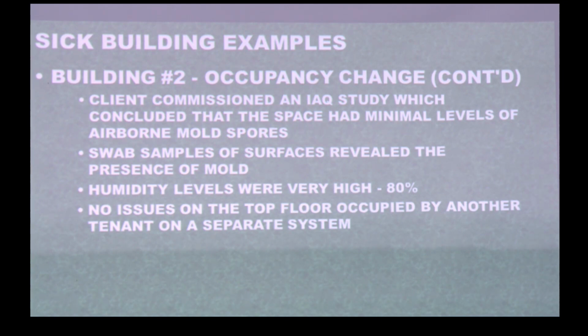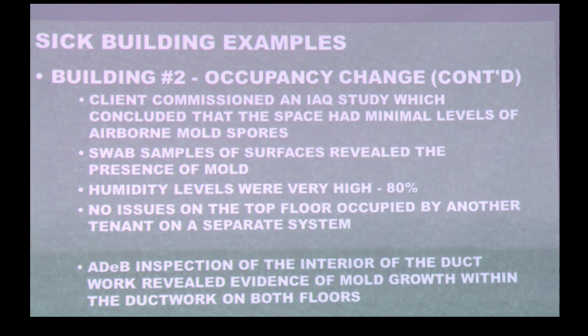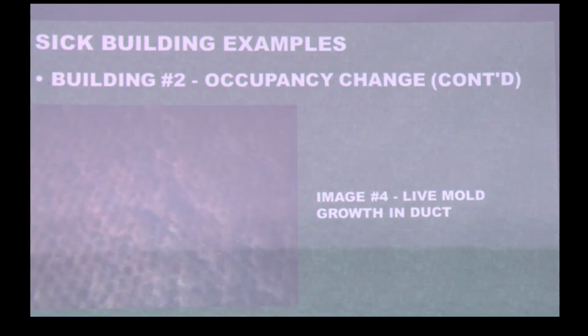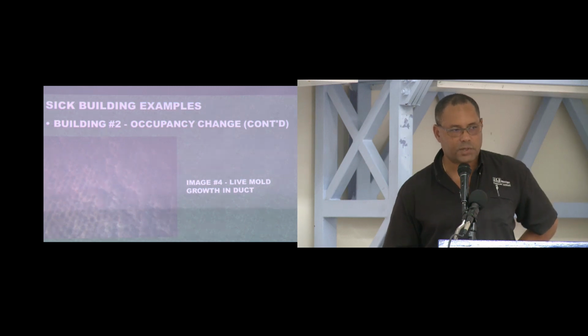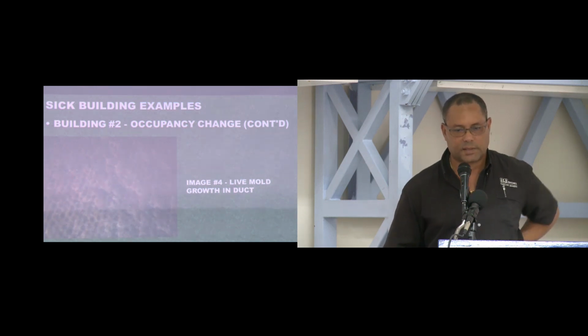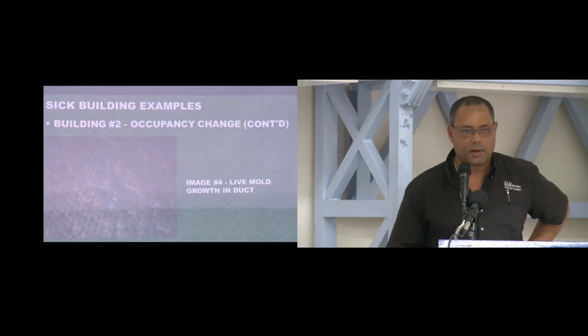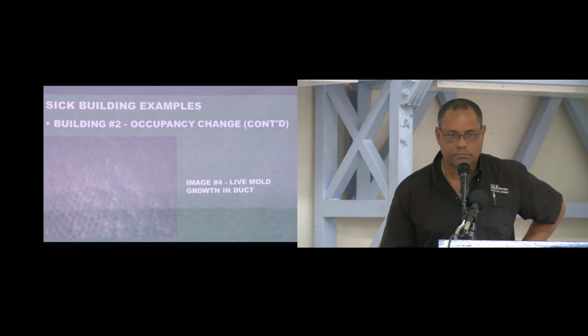So what is the story here? Well, our inspection of the ductwork revealed this. Remember that orange picture before? This is green. This is mold on the internal surfaces of the ductwork. The AC contractor had installed UV lamps in the air conditioning units, had recommended fumigation, all these fancy things. But this is live mold in your air distribution system. I'm not sure that UV lights can deal with this.